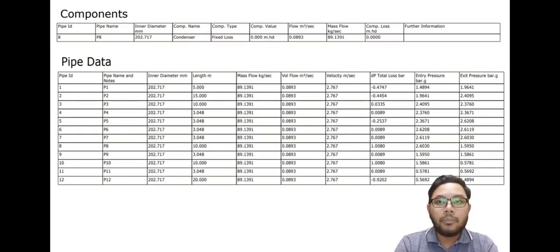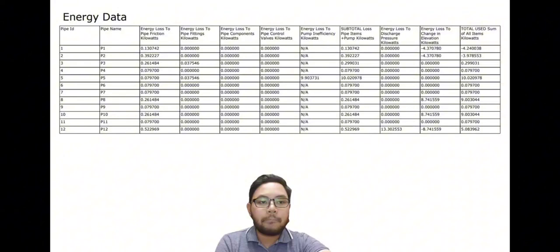For the pipe data, the inner diameter is 202.717 millimeters, while the minimum length for the pipe is 3.048 meters, and the maximum length of the pipe is 20 meters. For the velocity in the simulation, we get 2.767 meters per second. Lastly, here is the result of energy data for our simulation.